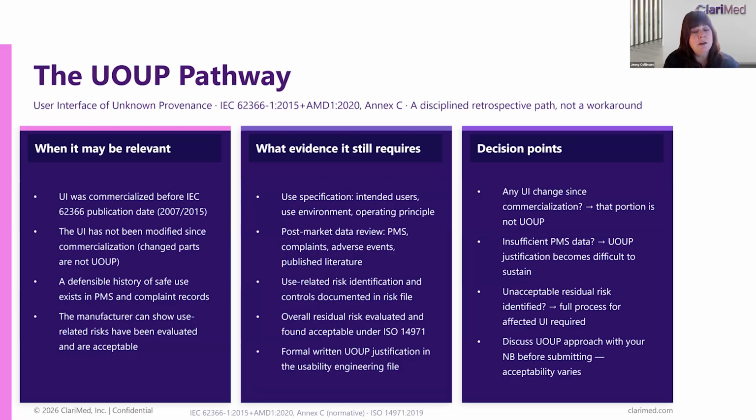And the other thing is, it's not an appropriate route if the user interface has changed fairly recently, because what you're using to generate the evidence is post-market data. So if the product that's in market is different to the product that you're currently trying to provide justification for, then there's no evidence.